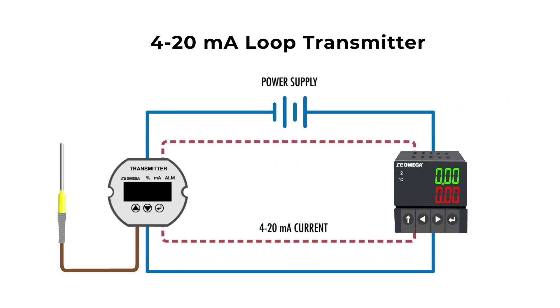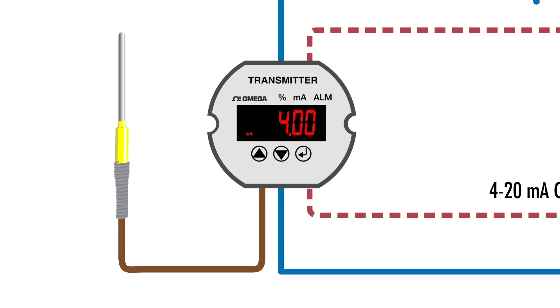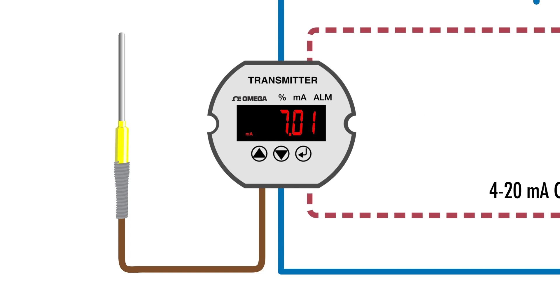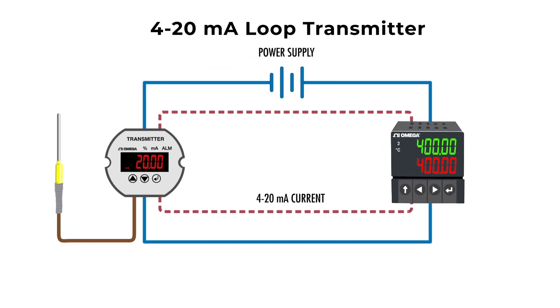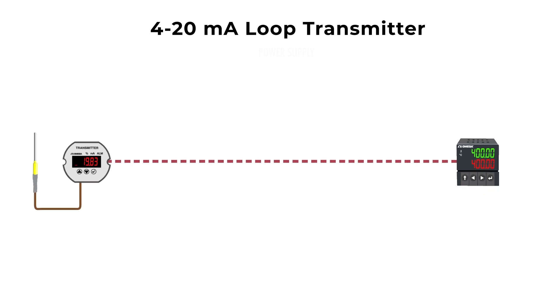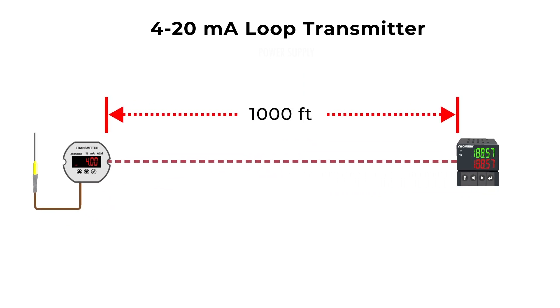A 4 to 20 milliamp loop transmitter is often a low cost and effective solution. The signal is converted to milliamp output, with 4 milliamps representing the low end of the measurement, and 20 milliamps representing the high end. Milliamp current signals can travel up to 1000 feet without being affected by signal loss due to electrical noise.